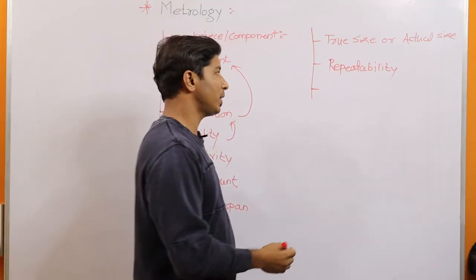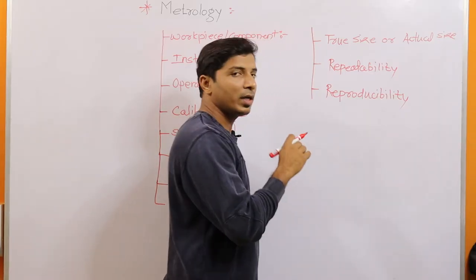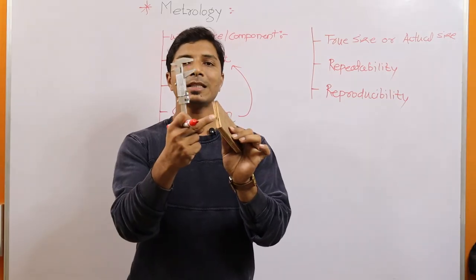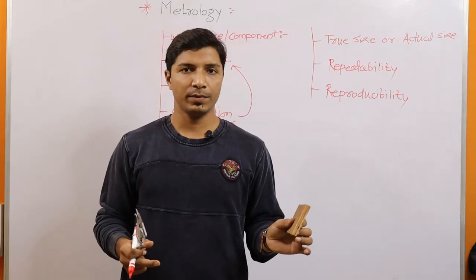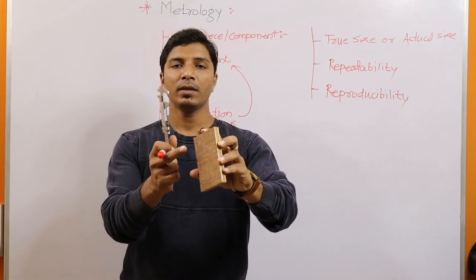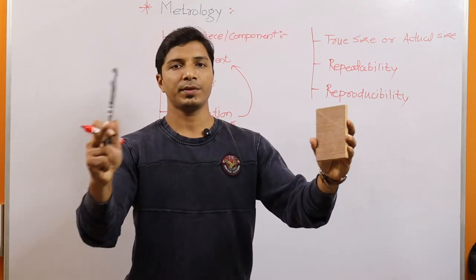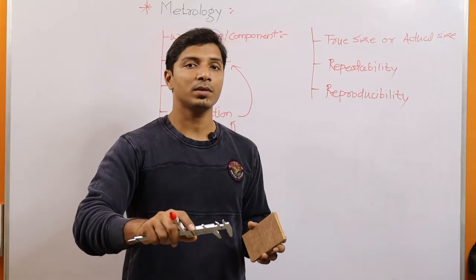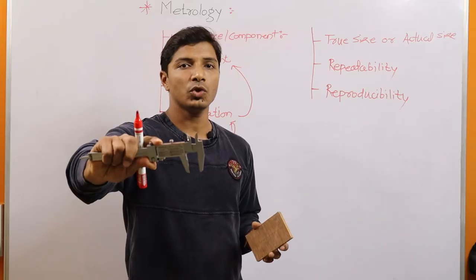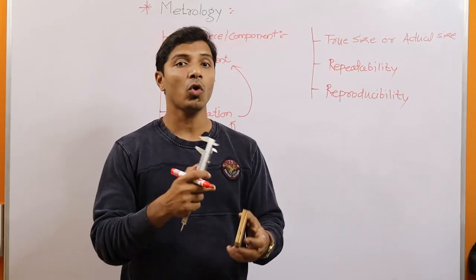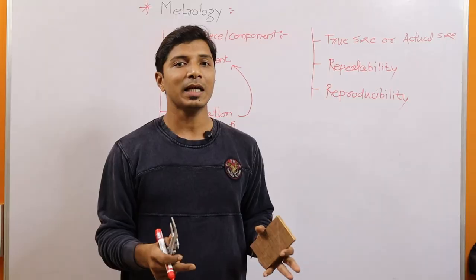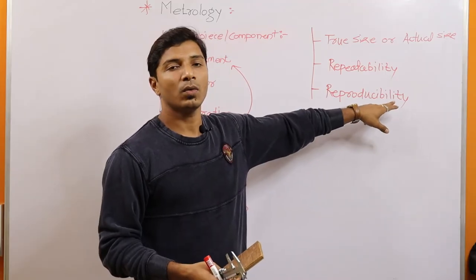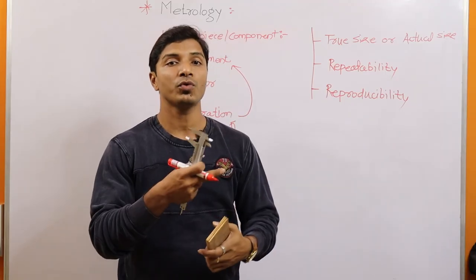Now, reproducibility: to understand this, assign the same dimension to be measured 20 times by three different operators, using a single instrument or different instruments. If the readings coming from all operators are close together, then those results are called reproducible or have reproducibility.